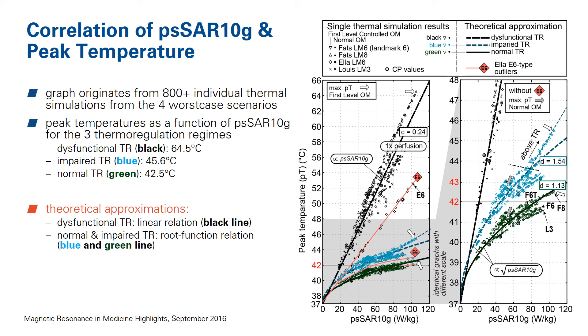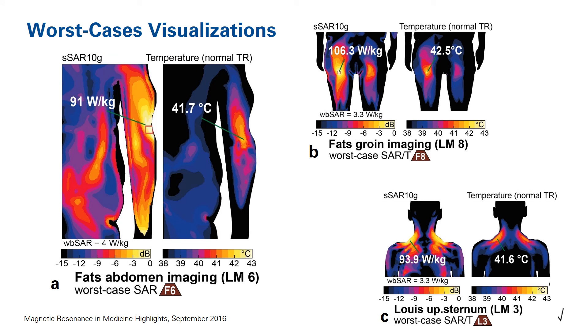Some visualizations of these worst cases: in Fats in the abdomen imaging position, hotspots occur in the arm at about 90 W/kg local SAR, corresponding to 41.7°C. Fats in groin imaging was already discussed. There is also a distinct hotspot in Luis in upper sternum imaging, where 93.9 W/kg results in a 41.6°C local peak temperature.